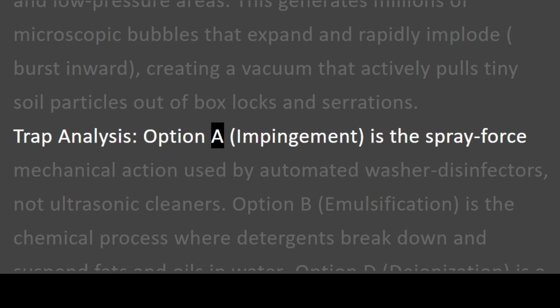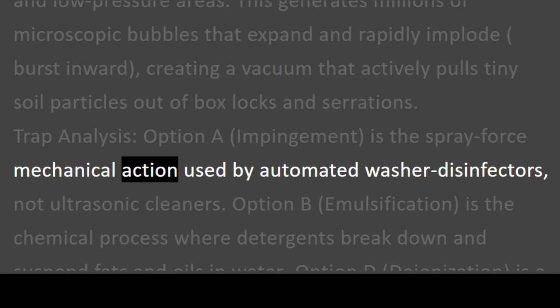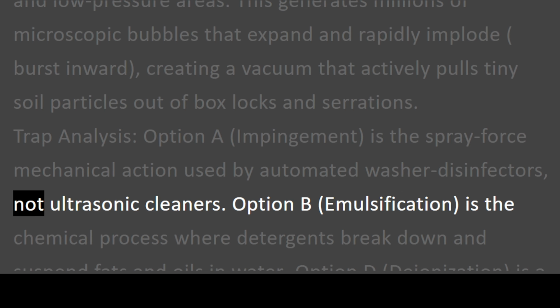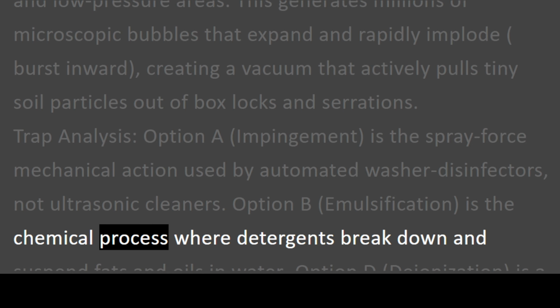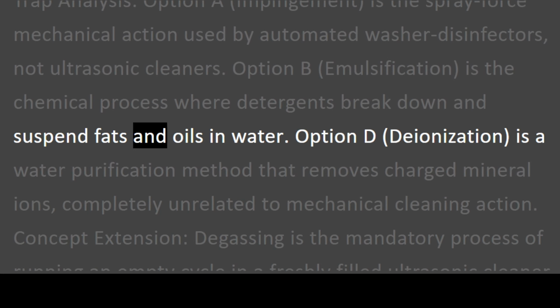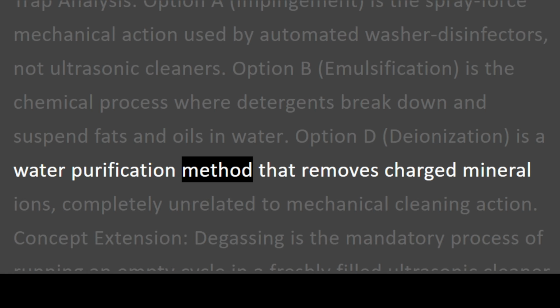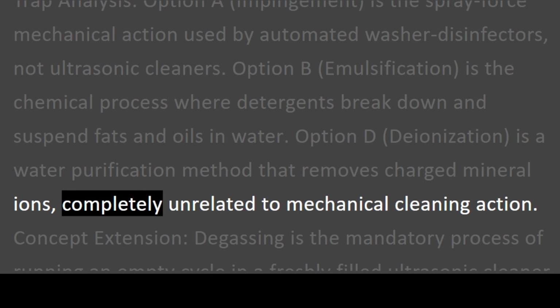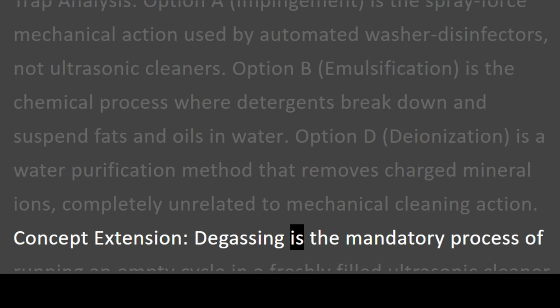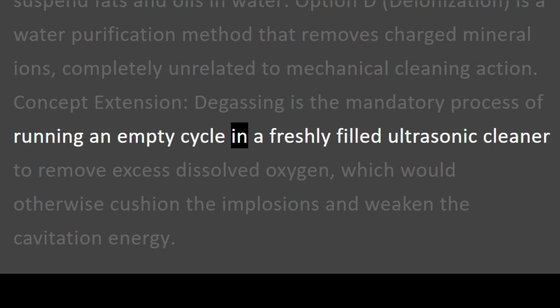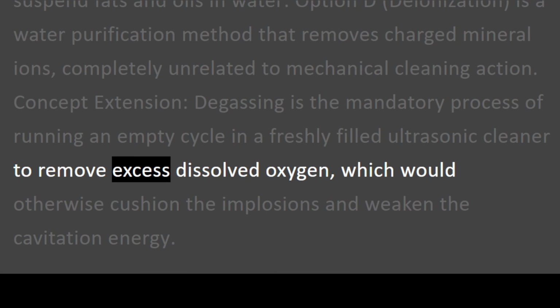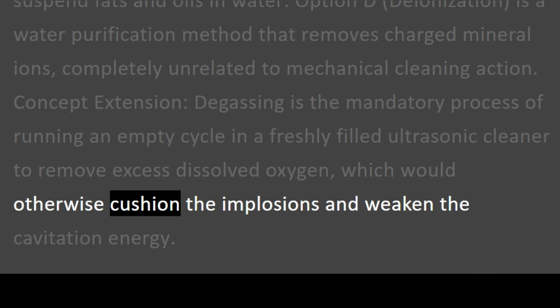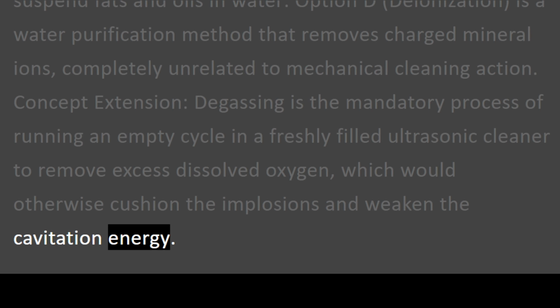Trap analysis. Option A, impingement, is the spray force mechanical action used by automated washer disinfectors, not ultrasonic cleaners. Option B, emulsification, is the chemical process where detergents break down and suspend fats and oils in water. Option D, deionization, is a water purification method that removes charged mineral ions, completely unrelated to mechanical cleaning action. Concept extension. Degassing is the mandatory process of running an empty cycle in a freshly filled ultrasonic cleaner to remove excess dissolved oxygen, which would otherwise cushion the implosions and weaken the cavitation energy.